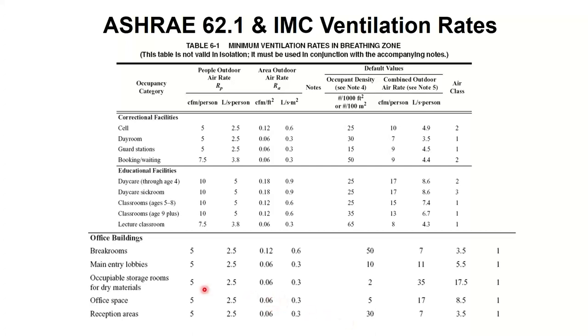Some buildings will require more. We just looked at an office building, but if I look at a classroom, it's literally double. Instead of 5, it's 10 per person. Instead of 0.06, it's 0.12 per square foot. A classroom requires double the amount of ventilation air as opposed to an office building with the same amount of people and square footage.